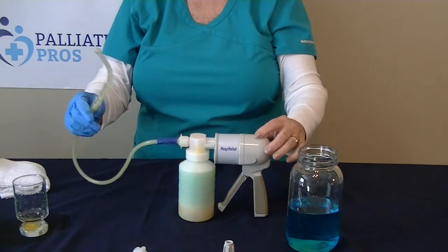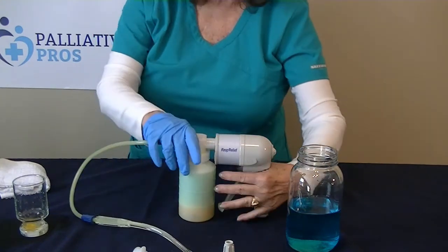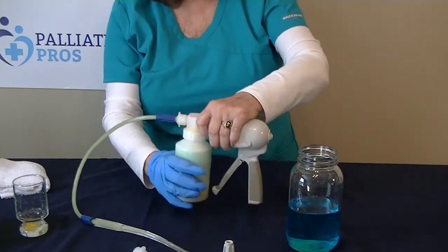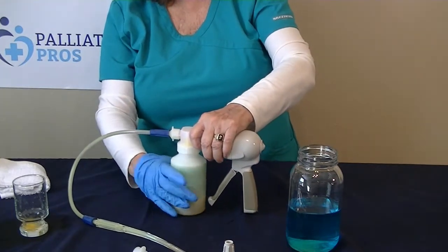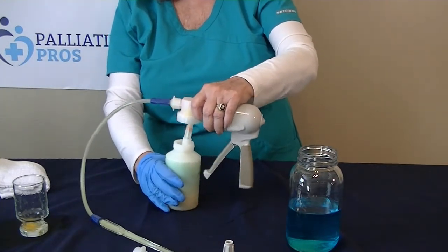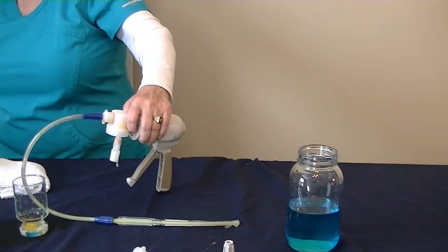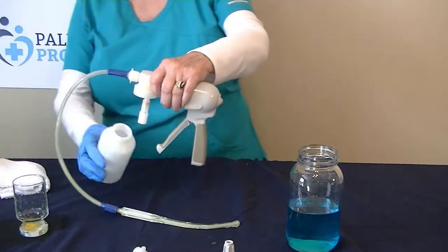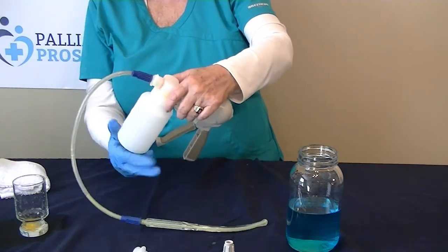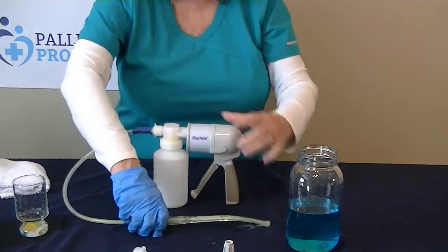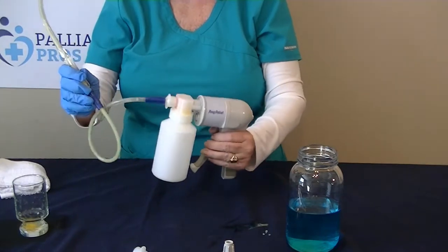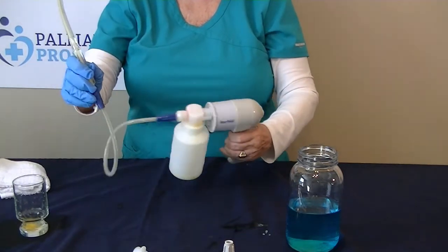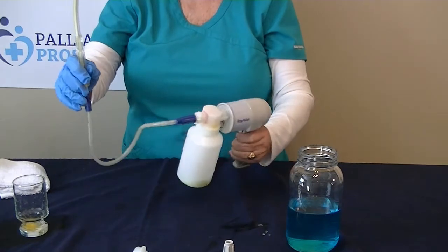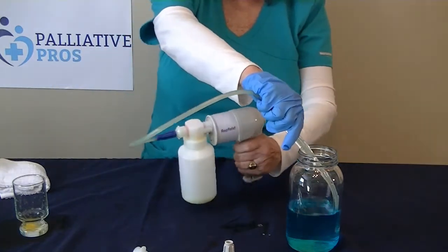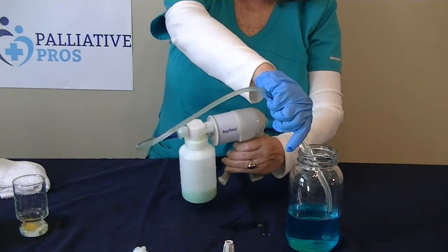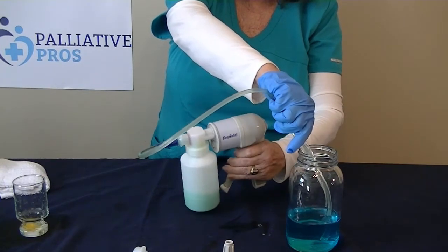In the event that the pump handle locks and the collection canister is not full, it may mean there is an obstruction in the tubing or in the device. If there is a visible obstruction, replace the tubing. And when this happens, gently tap the canister on a table. This should clear the obstruction inside the device. In the event the obstruction does not clear, replace with a new jar. And it's as easy as that.